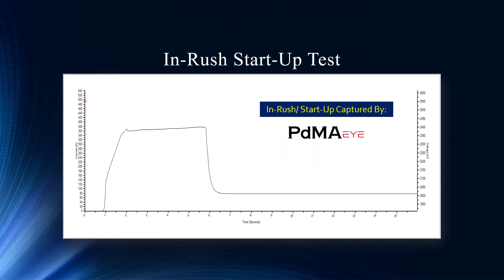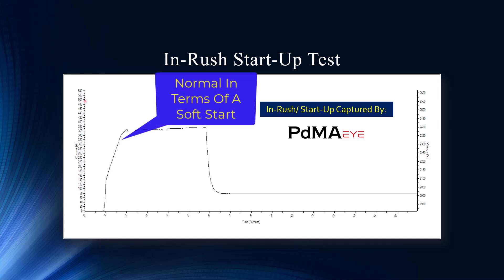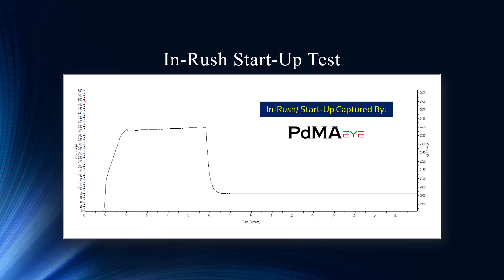Let's look at this one — this is a normal in-rush startup taken once we installed the PdMA Eye. This looks pretty normal. For seasoned veterans using the PDMA EMAX technology capturing in-rush, you notice there's really no in-rush here — just a gradual ramp up to startup current. What we have here is a soft starter, which controls the amount of voltage and current applied and ramps it up, so there's no major crushing of high current. It's about five seconds from beginning to steady state.